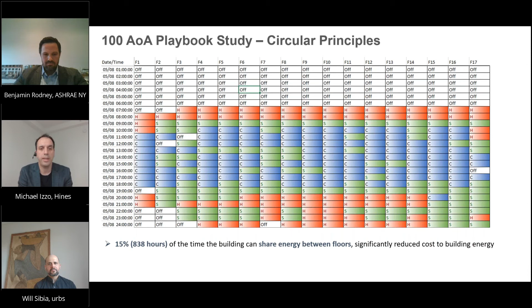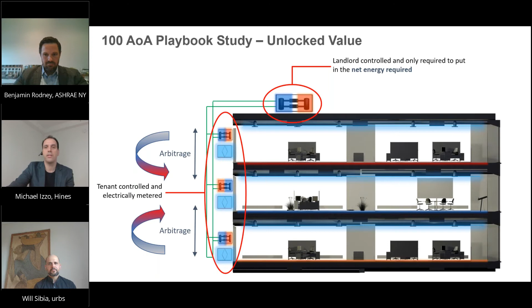This maybe describes it a little better: we have different devices, heat pumps, on each floor. If you think about even a DX building today, you have heat pumps stored within an air handler. Here we broke up the air handler and separated it into its independent parts—a water source heat pump and a DOAS unit—connecting the loop and closing the loop. Now we have sharing of energy between each floor, and the peak system at the roof only needs to supply the net energy required for the building.